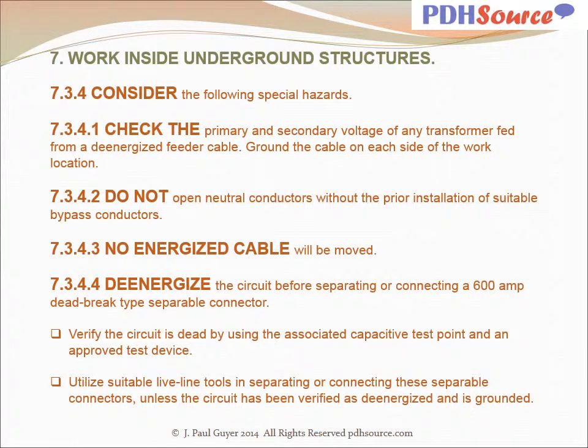Consider the following special hazards. Check the primary and secondary voltage of any transformer fed from a de-energized feeder cable. Ground the cable on each side of the work location. Do not open neutral conductors without the prior installation of suitable bypass conductors. No energized cable will be removed. De-energize the circuit before separating or connecting a 600 amp dead break type separable connector. Verify the circuit is dead by using the associated capacitive test point and an approved test device. Utilize suitable live line tools in separating or connecting these separable connectors unless the circuit has been verified as de-energized and is grounded.